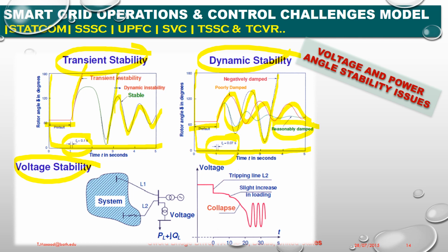In voltage stability, if you see here, this is my line number 1 and line number 2. Here is my power source and this is my voltage. Now it is showing voltage versus time. If my line number 2 is tripped for any reason, there is a slight increase in the loading, the voltage starts decreasing, and after 15 seconds the voltage collapses. So this is how the three stability types impact power system operation.